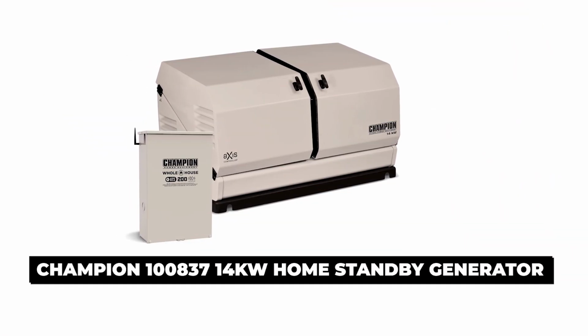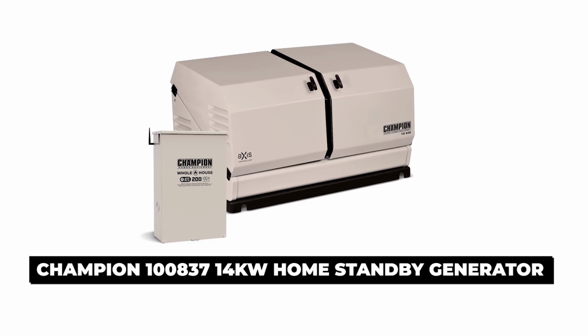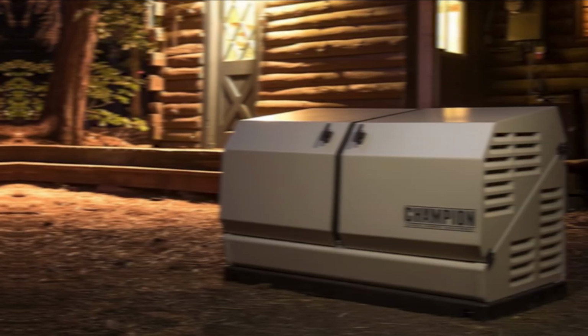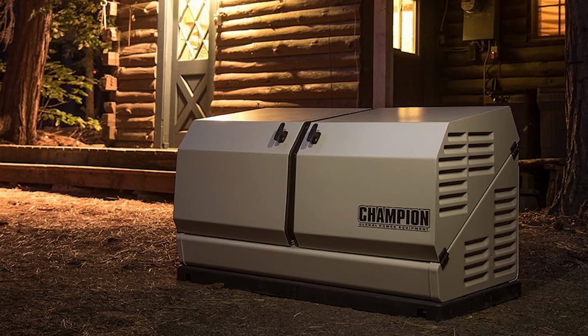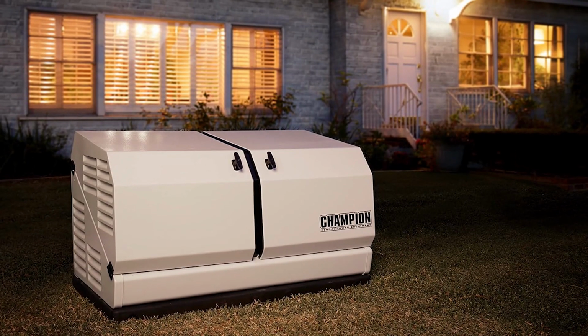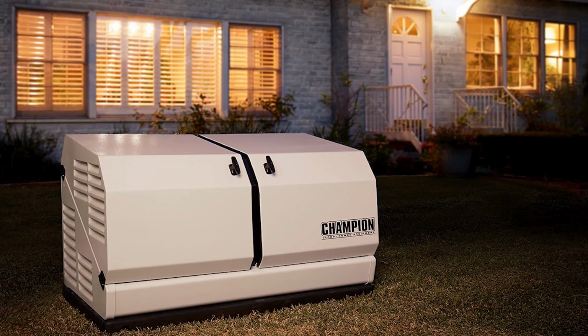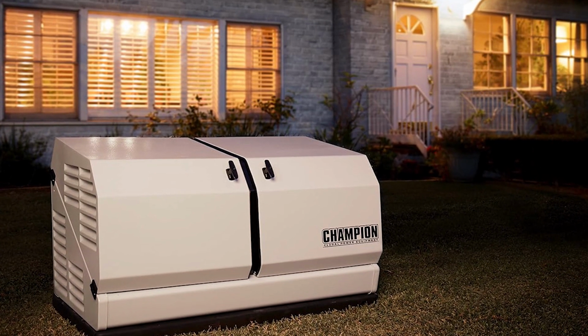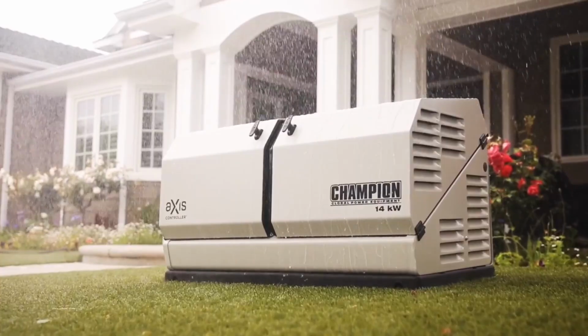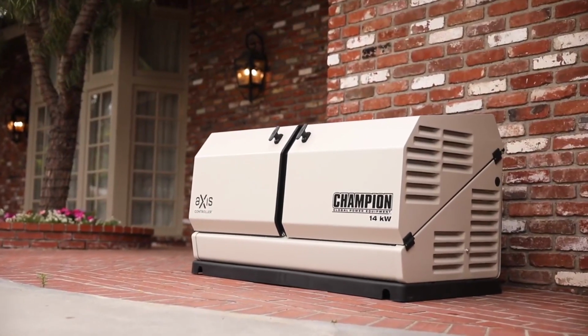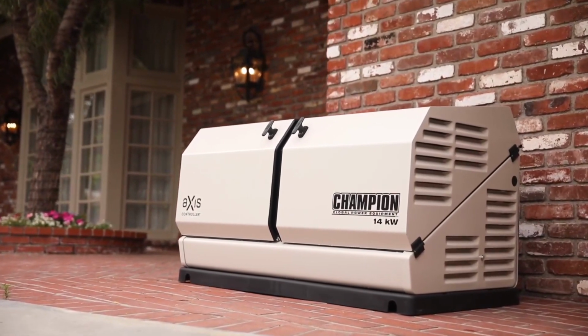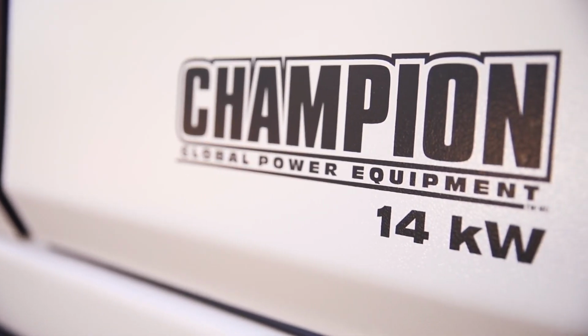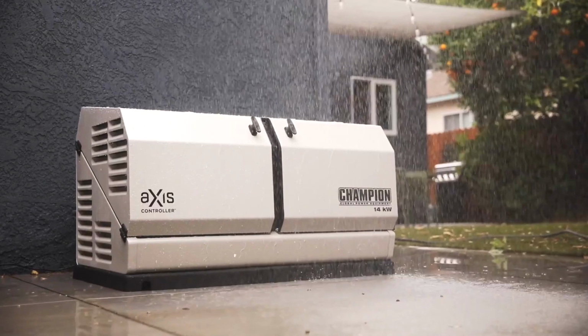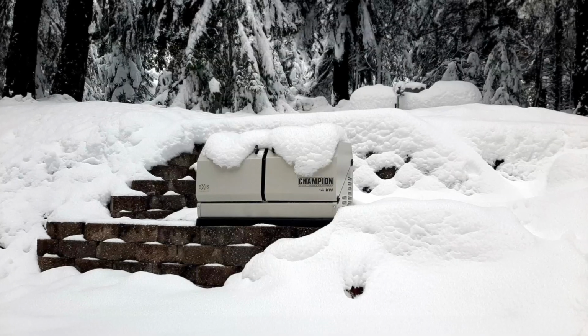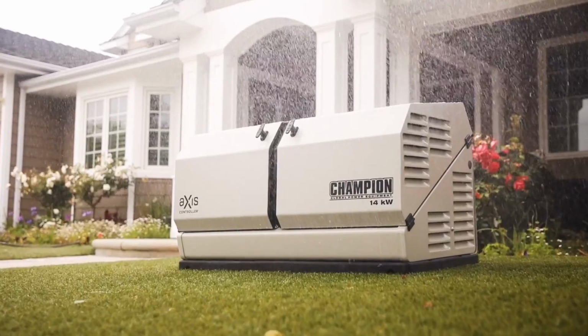Number 3 is the Champion 100837 14 kilowatt home standby generator. What makes Champion's system stand out is its communication technology. The eXis controller uses your home's existing electrical wiring to talk to the automatic transfer switch. No separate communication cable to run during installation. That makes the setup significantly simpler and cuts down on installation cost. You still get a 200 amp whole house transfer switch and 14,000 watts of output. If you want a smart, capable system that's easier to install than most, the Champion is worth a close look.